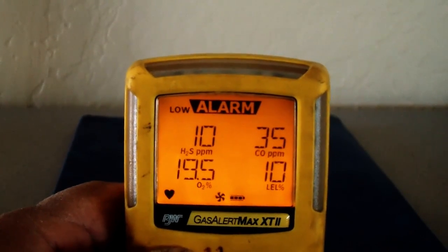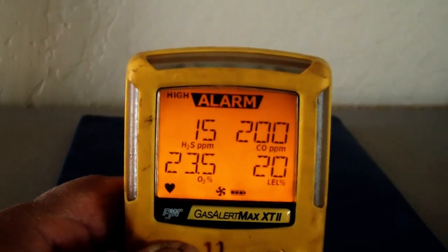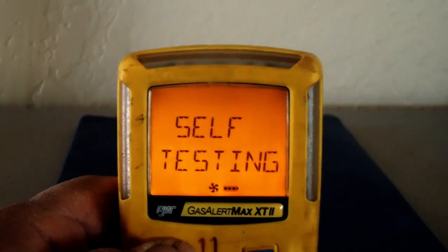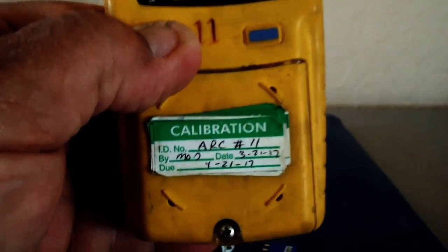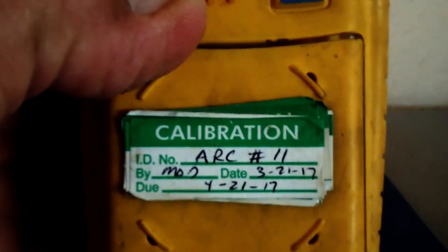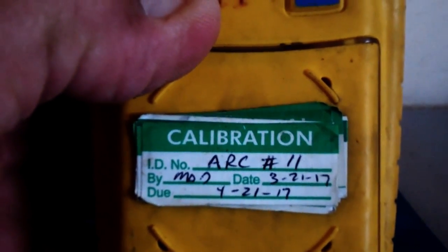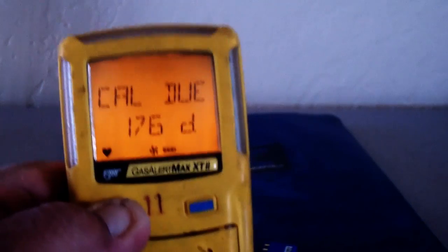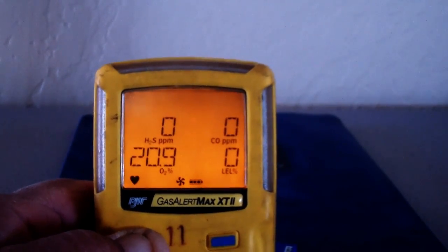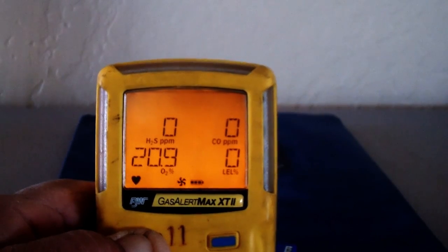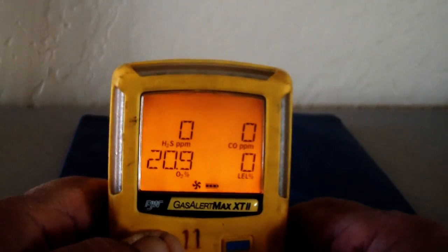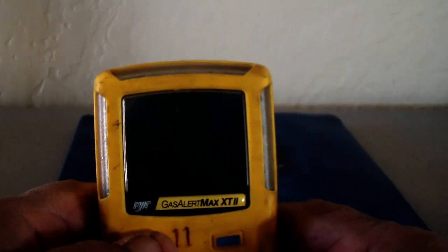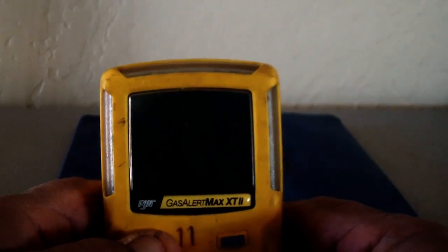So when my guys get into the shop in the morning and they go through the meters for the day, if they are within calibration or within 30 days of the calibration tag, they don't necessarily have to calibrate it. However, they do have to bump test it. During that bump test process, if we can't get this meter to bump out correctly, we're going to go ahead and put a calibration on it. So oftentimes these machines will be calibrated more than once every 30 days, depending on what is required. So to go into the calibration mode, it's pretty simple.